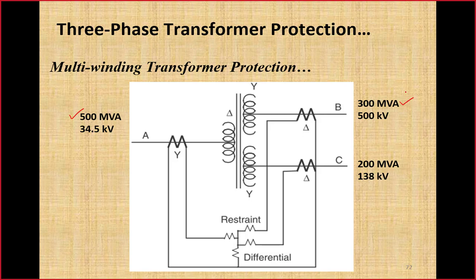Remember, in that way our results will be incorrect. The reason is that when there is no third winding C, both windings will carry equal power. So how can we do the calculation based upon the separate power ratings? The next student may ask, sir, then the maximum power that these two windings can carry when winding C is out of service is 300 MVA, because this transformer cannot carry 500 MVA, since winding B could not withstand power more than 300 MVA.